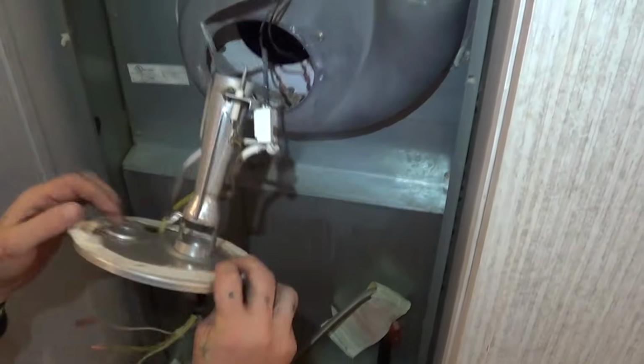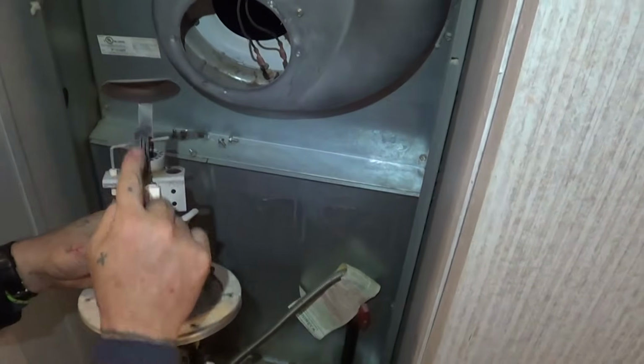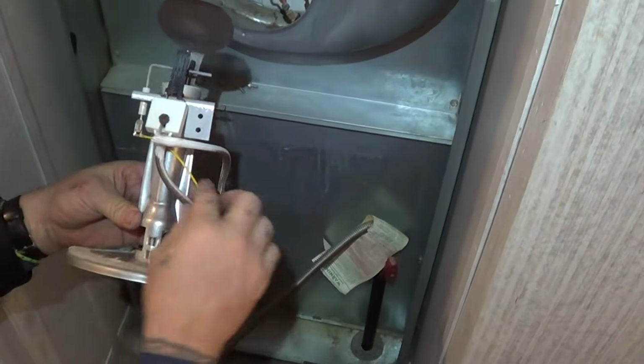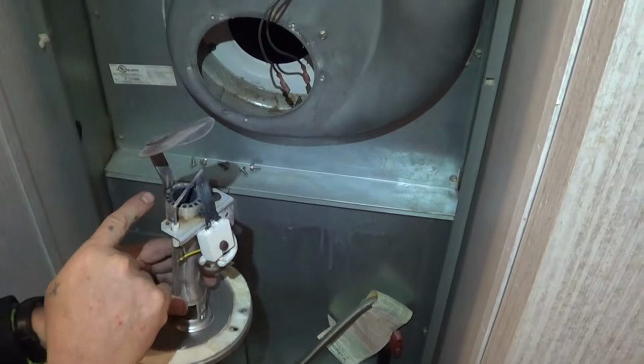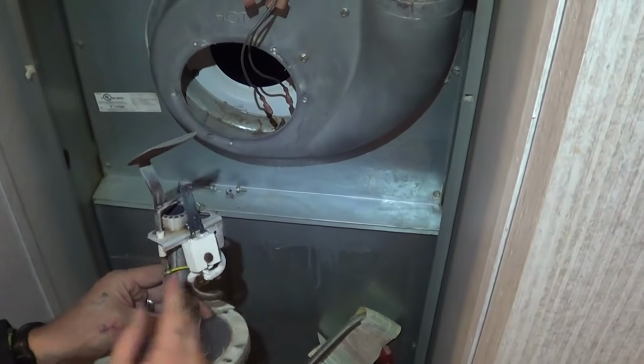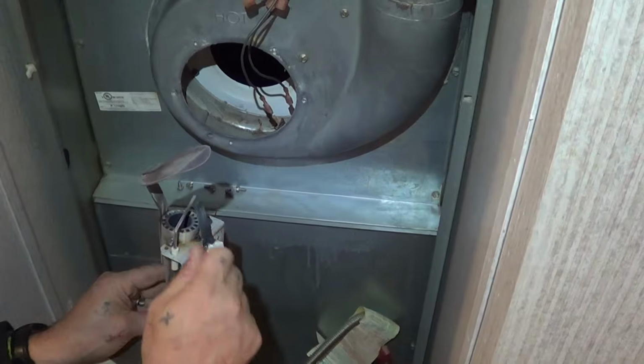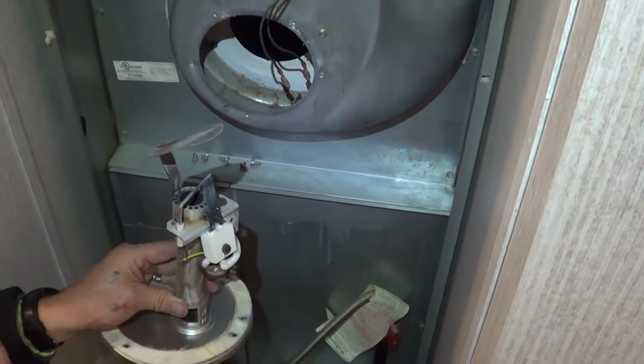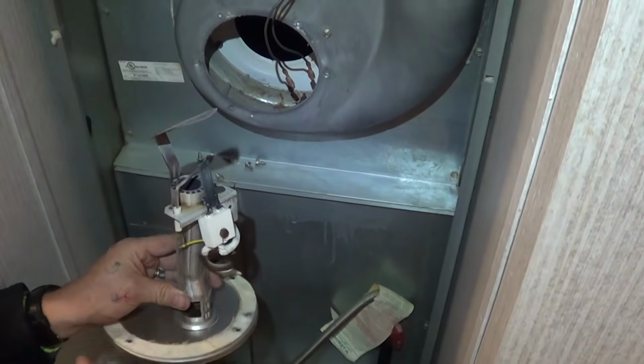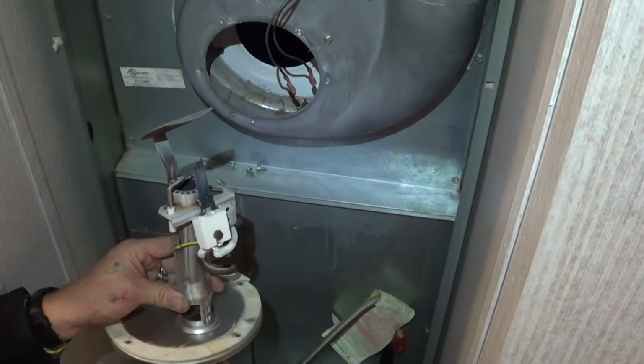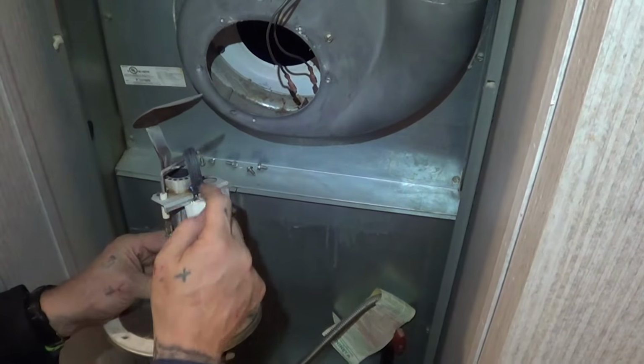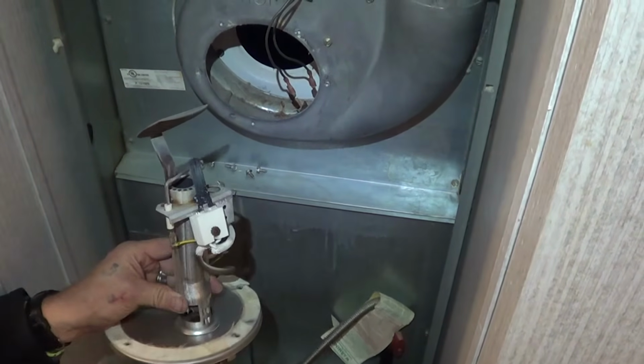And we're going to turn it around and look at this here. So right here we have the igniter. Here's the yellow wire going to the flame sensor. So if you get failed ignition on this, sometimes just clean that flame sensor really well with a little bit of sandpaper or something. Be real careful not to touch the igniter. If I went like that to the igniter, it would break. So don't touch it or anything, so be real careful with that.